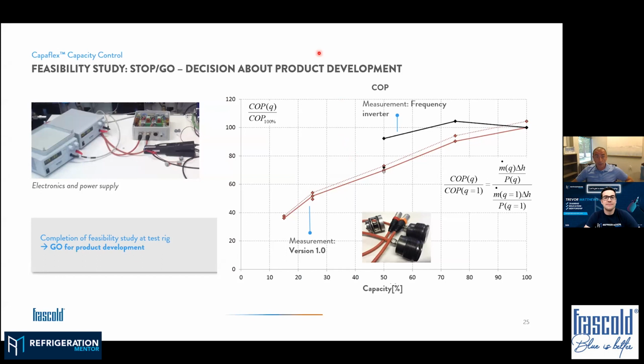So here on this slide, I just want to show you a little bit what was the design phase of the component in the past. First of all, on this chart, we have on the x-axis the capacity of the compressor, from a theoretical 0 to 100%. On the y-axis, we have a relative COP. So the base compressor is the compressor that has the COP calculated or measured in this case at full load. And so we made some measurements with a VFD down to 50%. In this case, we were running the compressor at a maximum of 60 Hertz, and this will be roughly 30 Hertz of frequency, therefore half the speed.